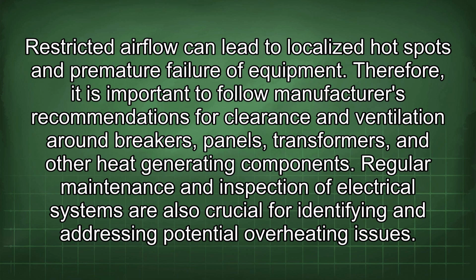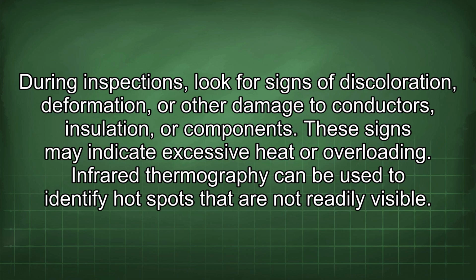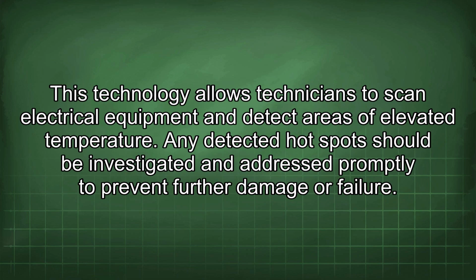Regular maintenance and inspection of electrical systems are also crucial for identifying and addressing potential overheating issues. During inspections, look for signs of discoloration, deformation, or other damage to conductors, insulation, or components. These signs may indicate excessive heat or overloading. Infrared thermography can be used to identify hot spots that are not readily visible. This technology allows technicians to scan electrical equipment and detect areas of elevated temperature. Any detected hot spots should be investigated and addressed promptly to prevent further damage or failure.